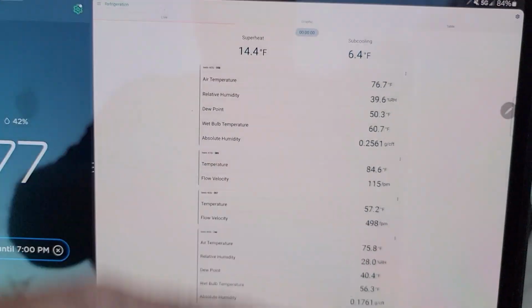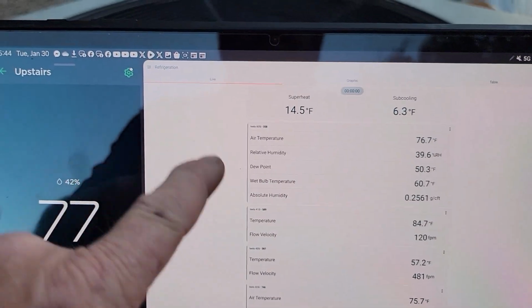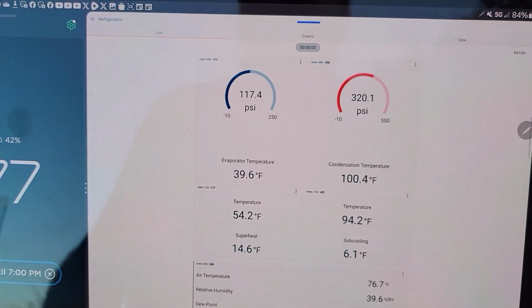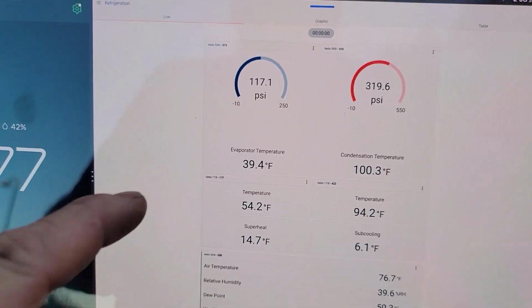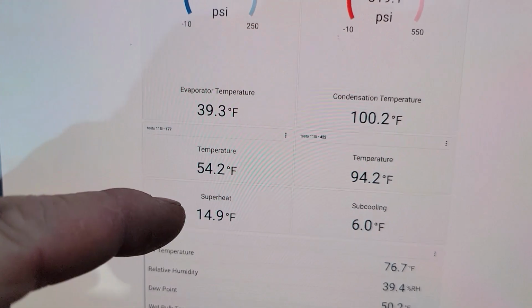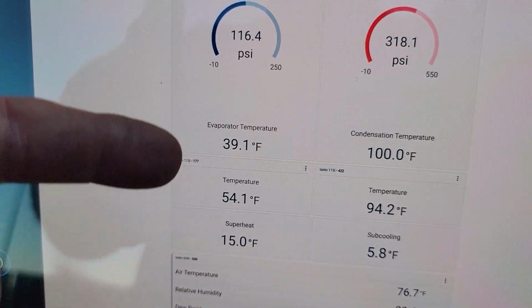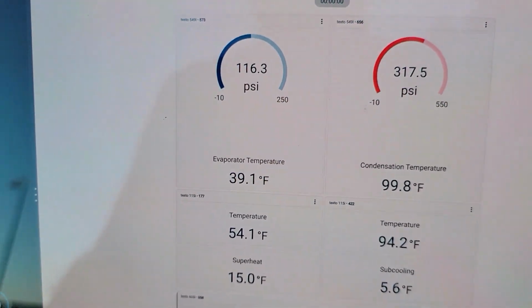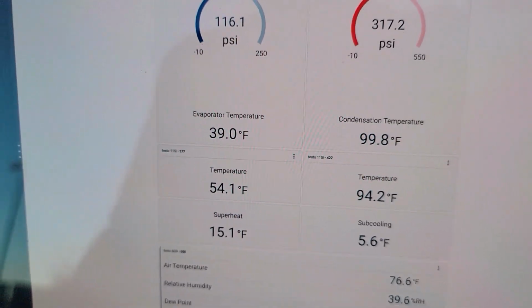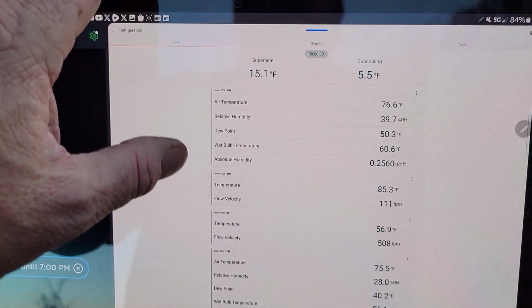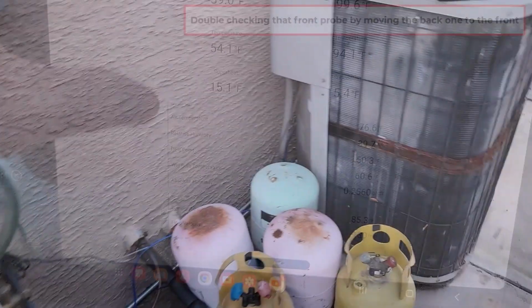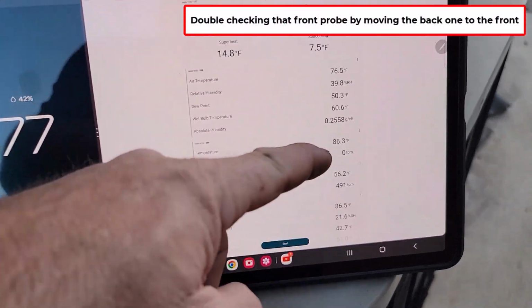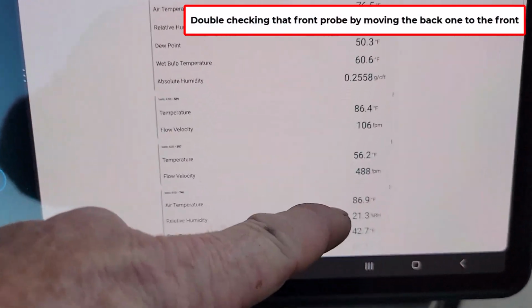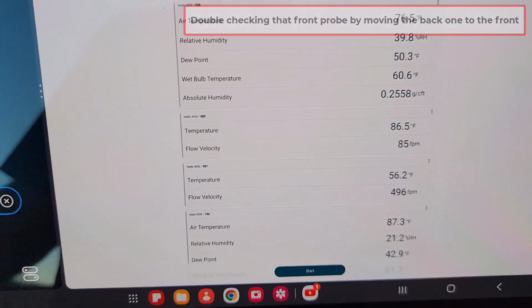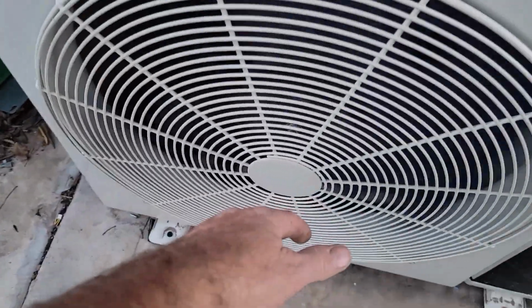So we're running 77, 57, about 20 degree split. Subcooling. I think I only got up to 8 or 9 degrees yesterday and then stopped there. See my superheat's correcting. Got a 54 degree line. Suction pressure is running 39. So we're good on the cooling. We'll run in another couple more minutes. I guess it was reading. It must be the one that says 86. Now this other one's reading 86 that I moved. It just feels way down.